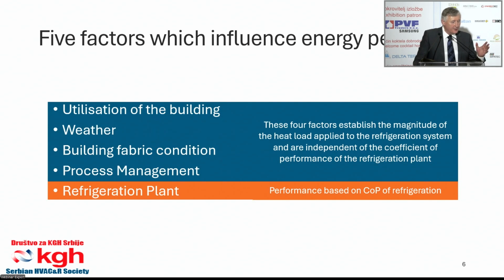And the performance is based on the coefficient of performance of the refrigeration system, which for many years people have thought, well, that's all that I need to worry about, is a good COP. I'll tell you one way to get a good COP in a cold store: leave the door open, because then the suction pressure will rise, the compressor will do a fantastic job, the COP will look really good, but your energy bill will be through the roof because your heat load is so high. You have to balance all 5 of these factors, attack all 5 of them, to get a good energy performance figure. And that means it's not only about the refrigeration plant, it's about all these other things as well.